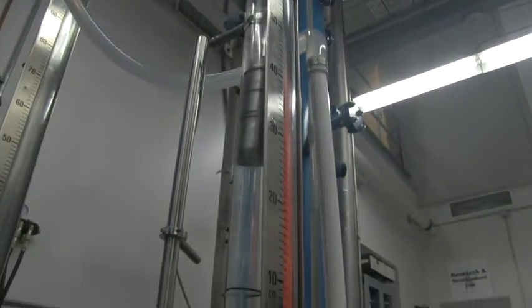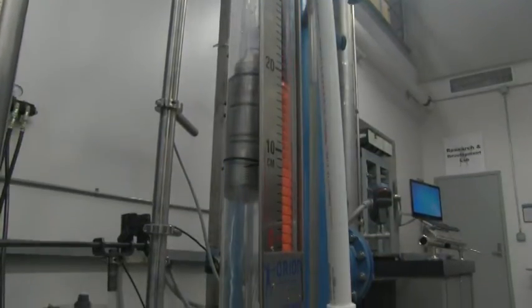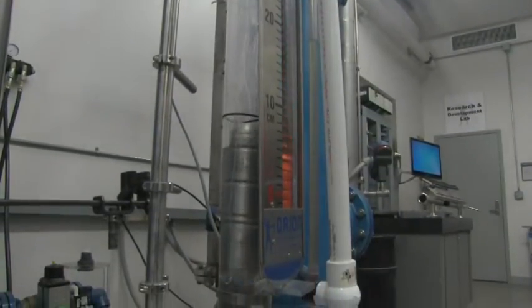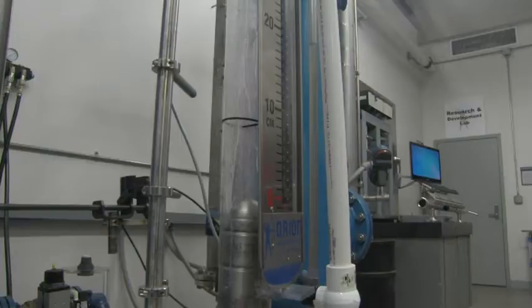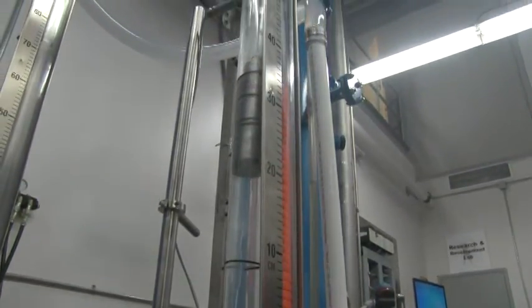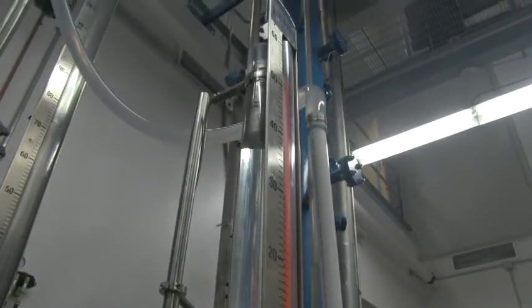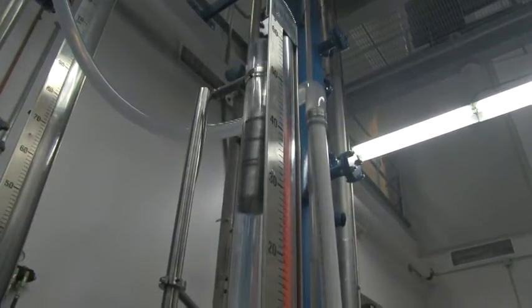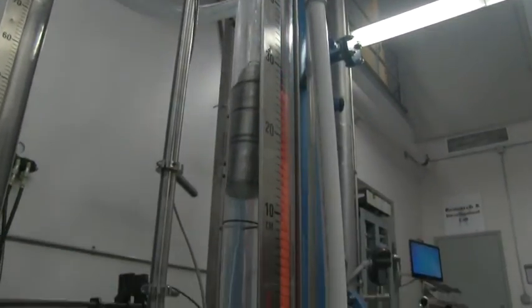This float contains an internal magnetic assembly that couples with the external visual indicator. The individual flags or flippers rotate 180 degrees as the level rises and falls, indicating the position of the liquid inside the MLI and therefore indicating the level of the liquid in the vessel.